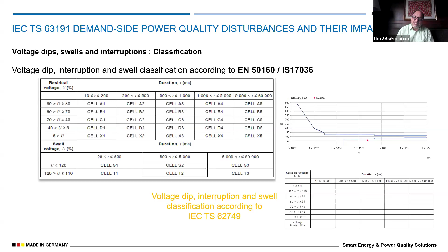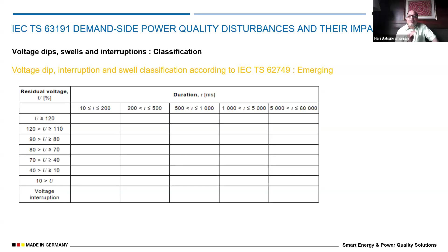This is the emerging standard which I have told you. It covers 10 milliseconds to 60,000 milliseconds, which is 60 seconds. How low the voltage goes needs to be recorded, and how many times. So in each cell you will get it: 3 times it went, 4 times it went. This forms a good report for anyone to understand how voltage sags affect the industries. You can compare it with your adjacent companies or industries, so that if they too have a similar situation, then both of you can go and talk to the utility, and they have to take action. If not now, later they have to take this action. But giving the data is very, very important.